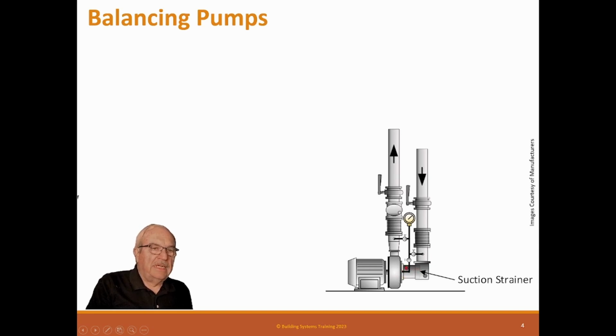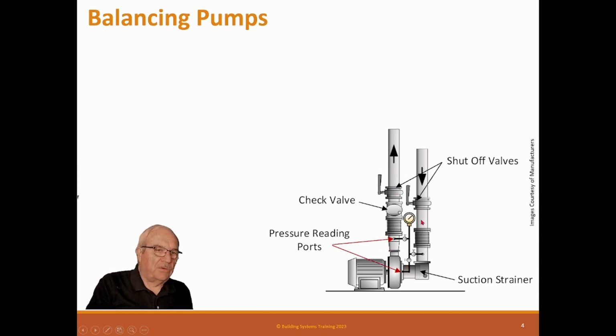Okay, so then the discharge goes up, and we have some isolation absorbers on here to prevent the pump vibration from going to the pipe. We have a normal check valve, and we have two shut-off valves. And I forgot to turn them on. There are the shut-off valves, there's the check valve, and these are the pressure reading ports. So this is a header. This is how we really like to see them. A designer may not do that. A designer may put a gauge here and a gauge here, and if that happens, then you'll need to revise that.